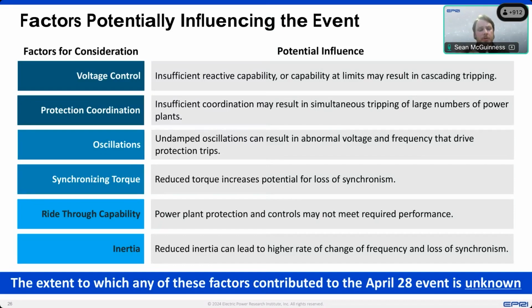We also recognize that ride-through capability and ride-through performance in particular are challenges. There have been a number of major events, particularly in North America, around power plants not riding through sustained undervoltage events or faults. In this case, obviously we don't know what happened, but there are quite well-defined ride-through requirements. Recognizing those, in coordination with protection coordination, and having a ride-through requirement is vitally important, but recognizing how the plants may respond to it is just as important.